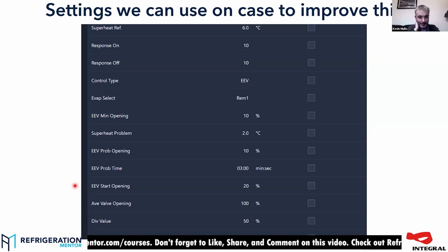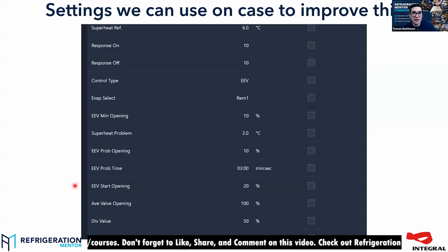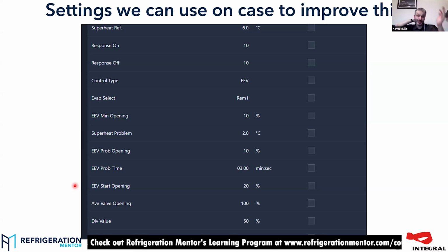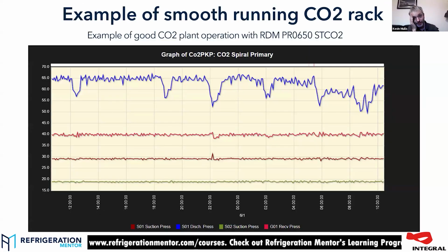Yeah, so we're talking about, like, I was at a cold storage transcritical system yesterday. The coils were 30, 40 feet in the air, and they were like 20 feet long, 6 or 8 feet deep. So these massive evaporator coils, that's going to be a little bit different than a plate heat exchanger. Yeah, oh, totally. Exactly. A plate heat exchanger is a great example of the fact you should start on a low opening, because there's no way you want to start on a 50% opening with a plate heat exchanger. That's a great example. So yeah, that's your main tools for that one.